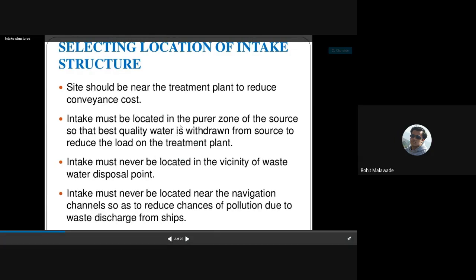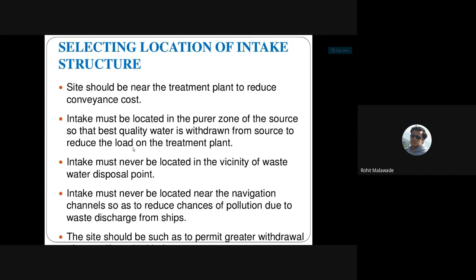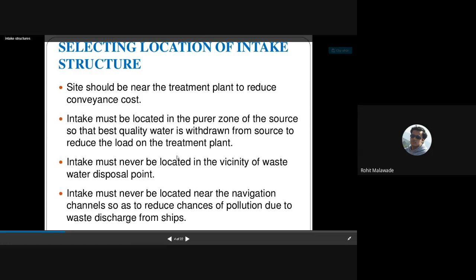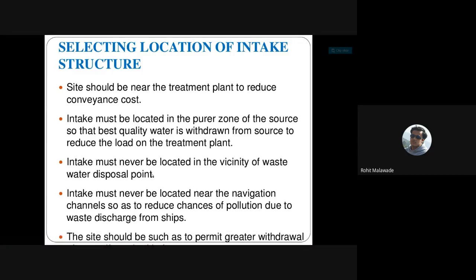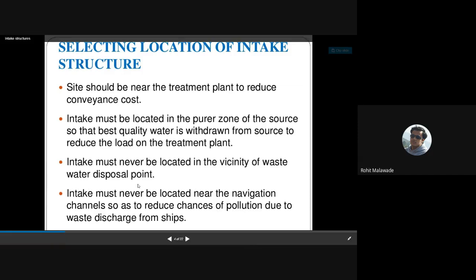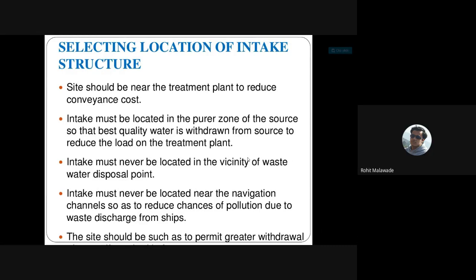The intake must be located in a purer zone of the source so that the best quality of water is withdrawn, reducing the load on the treatment plant. The intake must never be located in the vicinity of a wastewater disposal point. It should be free from pollution and should not be very near to a sewage disposal plant.